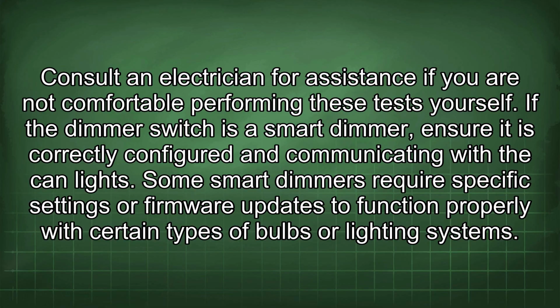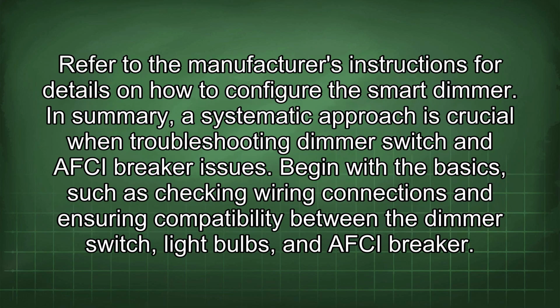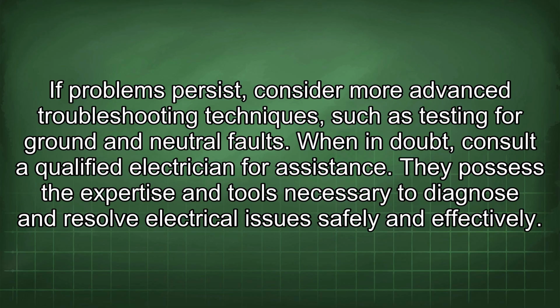If the dimmer switch is a smart dimmer, ensure it is correctly configured and communicating with the can lights. Some smart dimmers require specific settings or firmware updates to function properly with certain types of bulbs or lighting systems. Refer to the manufacturer's instructions for details on how to configure the smart dimmer. In summary, a systematic approach is crucial when troubleshooting dimmer switch and AFCI breaker issues. Begin with the basics, such as checking wiring connections and ensuring compatibility between the dimmer switch, light bulbs, and AFCI breaker. If problems persist, consider more advanced troubleshooting techniques, such as testing for ground and neutral faults. When in doubt, consult a qualified electrician for assistance. They possess the expertise and tools necessary to diagnose and resolve electrical issues safely and effectively.